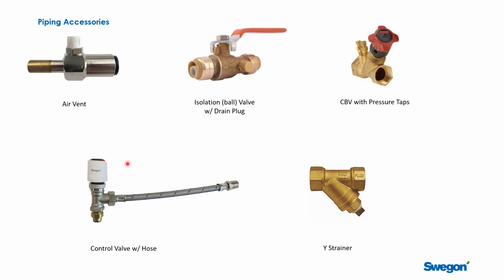And here's a picture of an assembly that would fit onto the coil. It's actually got a control valve built into it. They could be on, off, or modulating. Some of the control valves use what they call a hot wax. It's very popular in Europe. There's actually a little heating element in here and a wax in the actuator.